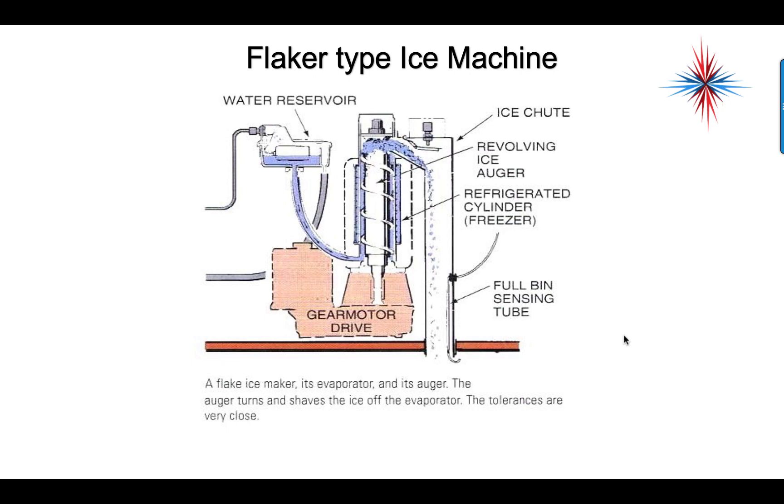Flaker type ice is a different process. We have our evaporator walls, which is the refrigerated cylinder. We feed water in the bottom, and there's an auger that is constantly running. As the water freezes on the walls, it flakes that ice off and shoves it down a chute into the bin. This auger has to be perfectly aligned, or it will destroy the evaporator. The main points of failure are the gears at the top and the bearings at the top and bottom. Once those are done, the ice machine needs to be replaced.